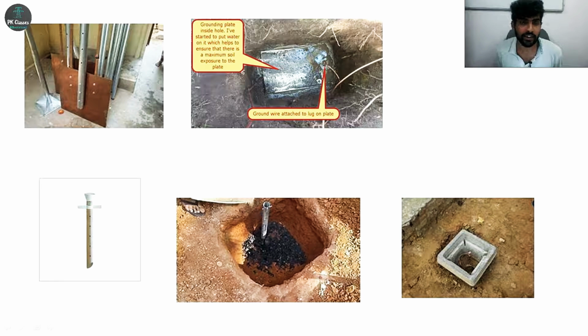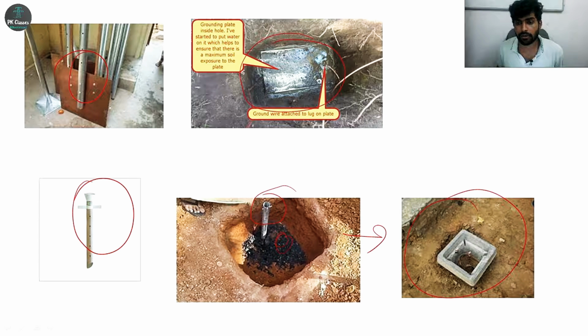There is a plate earthing electrode placed in the earth pit. There is a pipe earthing electrode placed into the earth pit. There is charcoal and salt present for increasing the conductivity of the soil. Finally, you can find this type of picture nearby your surrounding. This is an earth chamber, earth electrode wire here. Inside there is an earth electrode present. Chamber is for maintenance purpose.